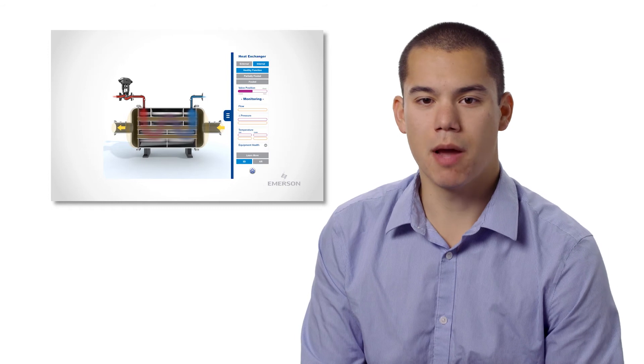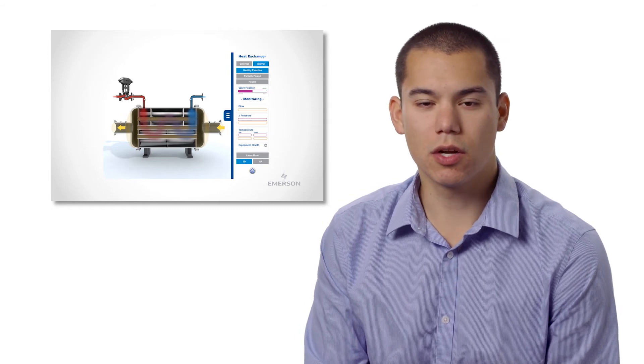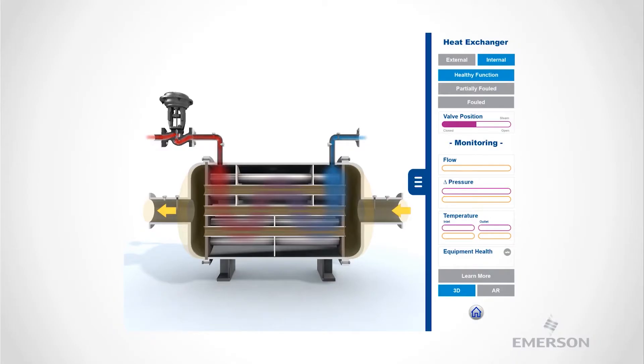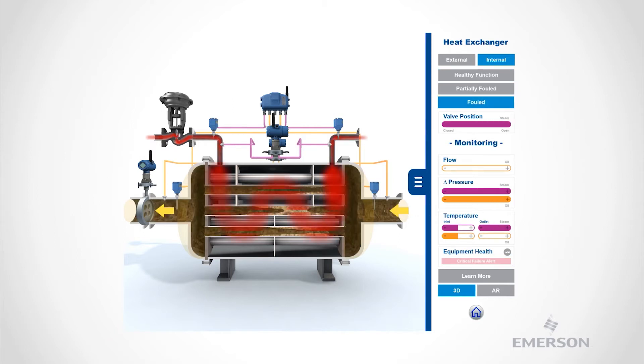The first step to Emerson's heat exchanger monitoring solution is to collect real-time data about heat exchangers. Temperature, flow, and differential pressure are all key measurements that can be captured using Emerson technology. PlantWeb Insight then gathers and analyzes the raw data to determine the overall health of a heat exchanger using pre-engineered algorithms and expertise. This includes whether the heat exchanger is experiencing fouling.